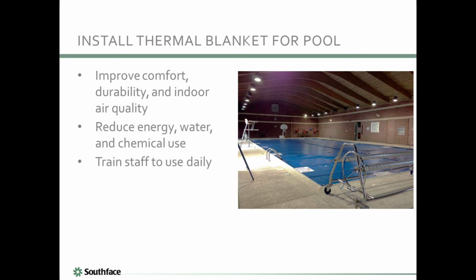One simple strategy that can reduce evaporation and resulting energy consumption is to install a thermal blanket when the pool is not in use. A thermal blanket is essentially a vapor barrier that is used as an impermeable pool cover. Covering the surface of the pool with a thermal blanket can reduce energy and water consumption by more than 30%. The cost savings for installing a thermal blanket at this natatorium are more than $13,000 per year. $13,000 for a piece of plastic.